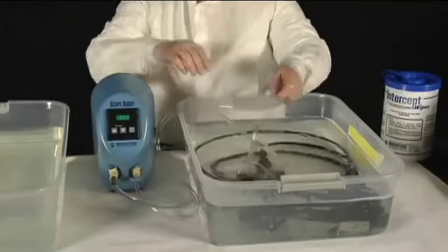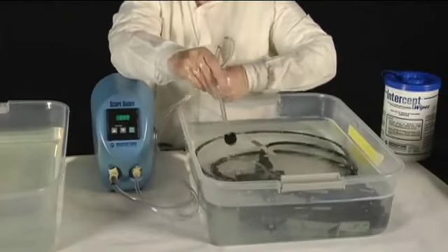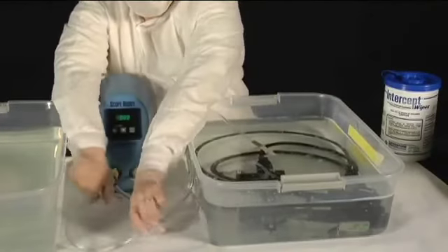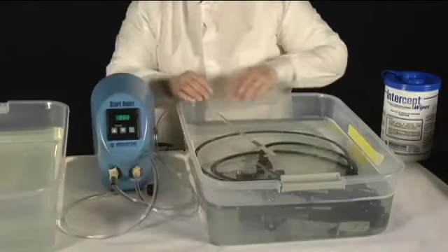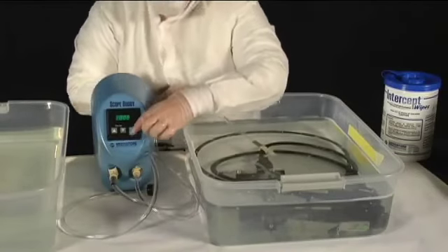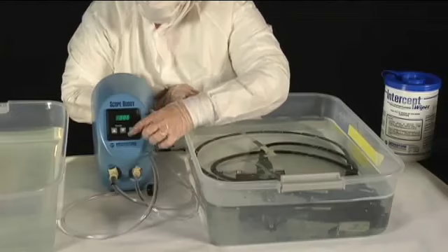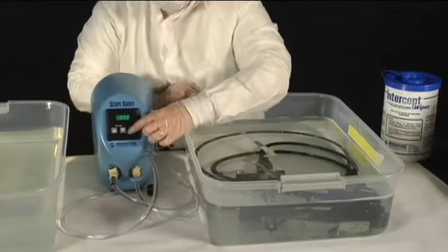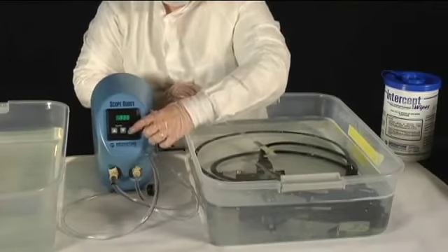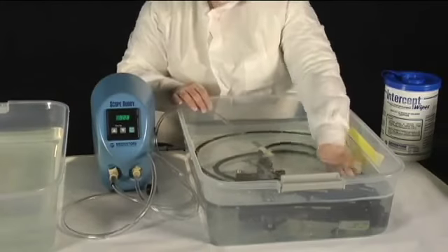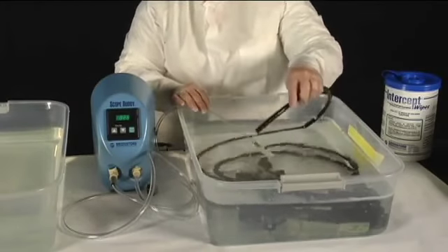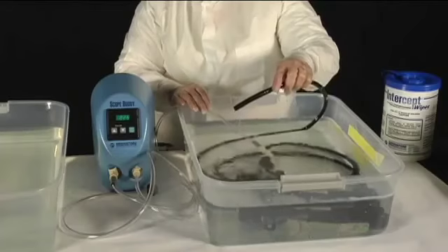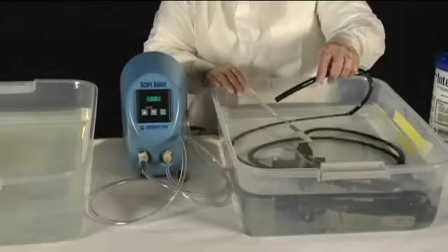To purge an endoscope of rinse water, remove the fluid intake line out of the rinse water. Press the Start-Stop button once to reset the timer to the original preset time amount. Press the Start-Stop button again to begin pumping air in order to purge the endoscope of rinse water. Press Start-Stop button to halt pumping when fluid no longer exits the endoscope.